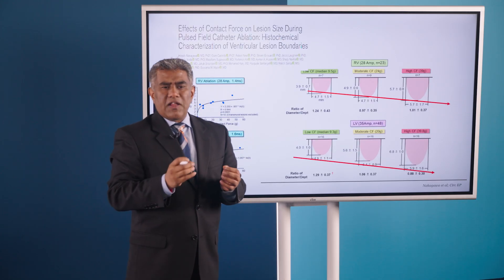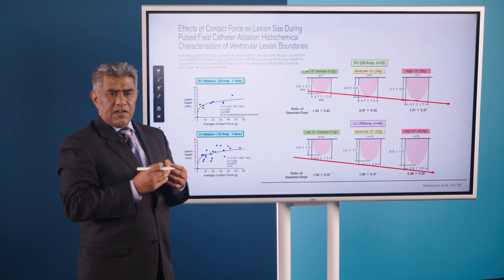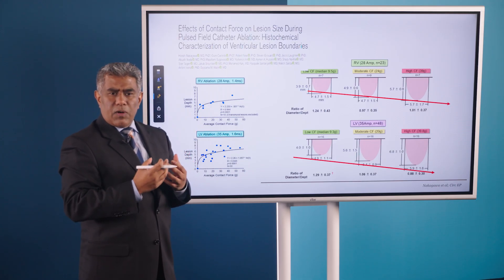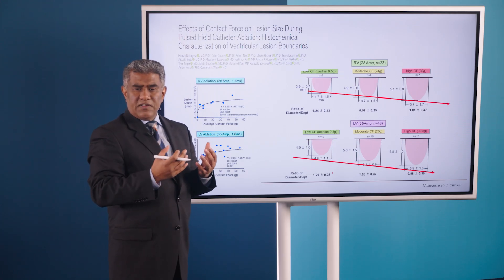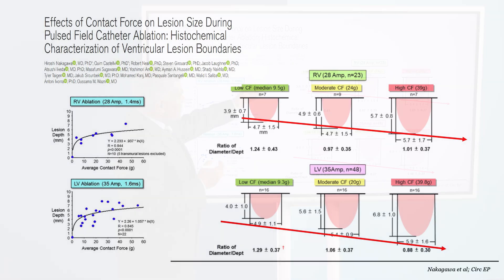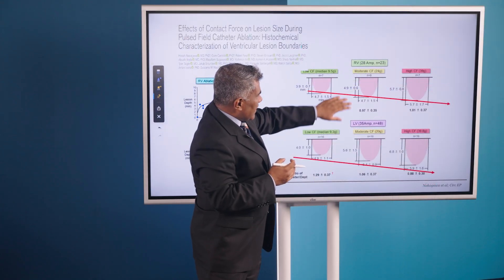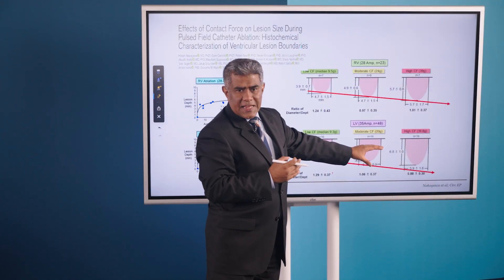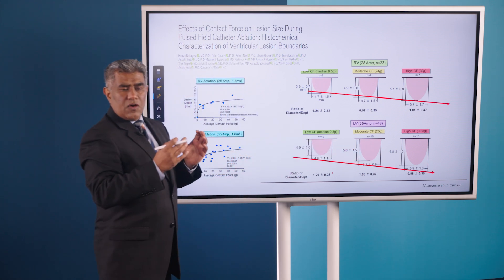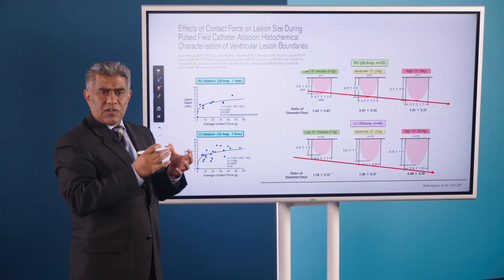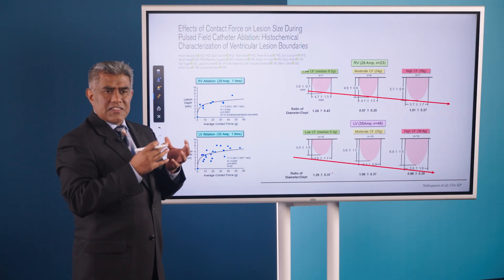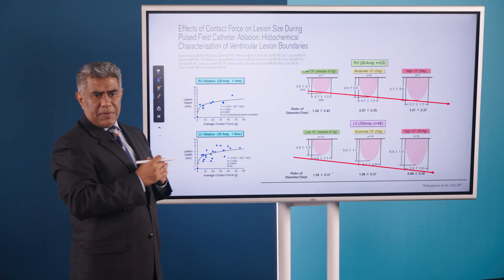When we talk about small catheters, such as a 3.5-millimeter-tipped catheter, there's been a lot of debate about the importance of contact force. There are some papers that say this is not that relevant, and some that say it is relevant. This is work from Dr. Nakagawa, who shows that with increasing contact force, both in the right ventricle and in the left ventricle, you have an increase in lesion depth. One peculiar aspect of pulse field ablation compared to radio frequency is that as you increase the contact force, it impacts the depth more than the width, as per this particular paper.